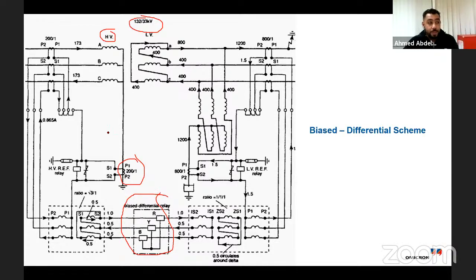So what I'm doing is I have a current here on the high voltage side. First of all, we calculate the full load current. Then, from the full load current, I need to decide the CT dimensioning, the CT ratio, so that I have a significant full load current. So we need to decide 200/1. And I need to take into consideration the directionality as well. Where is P2 and P1?